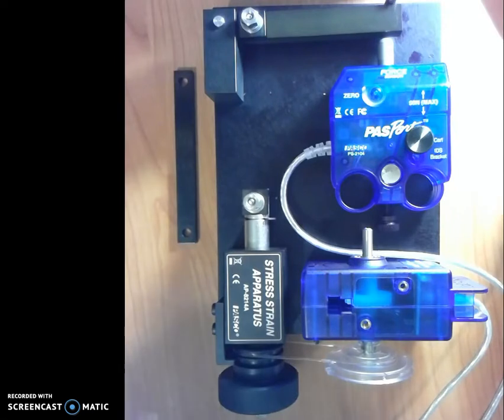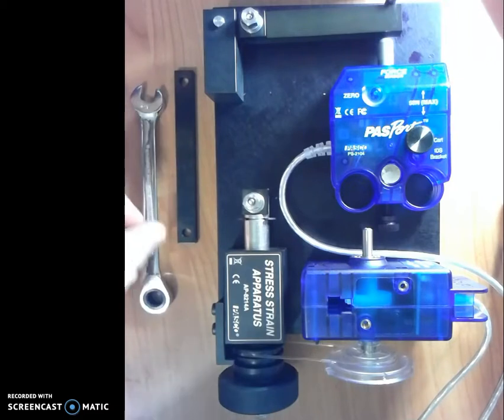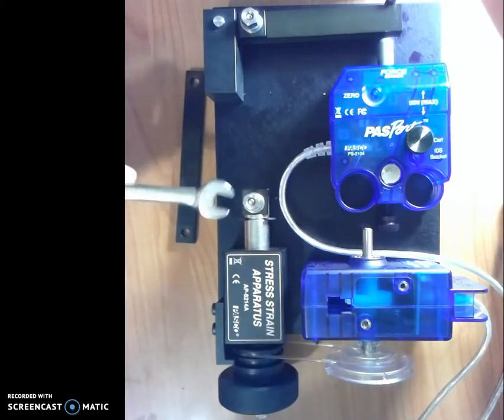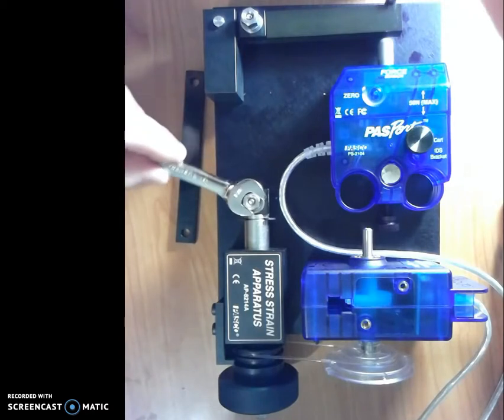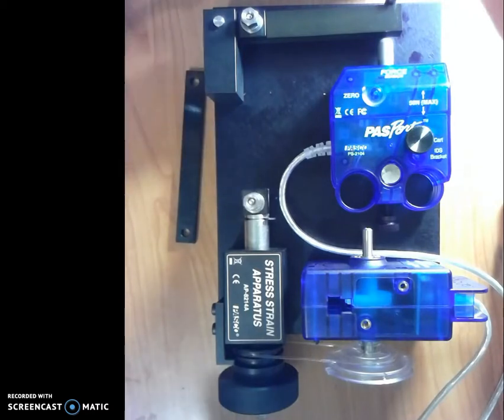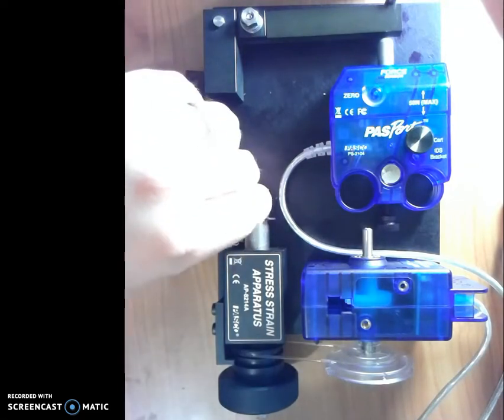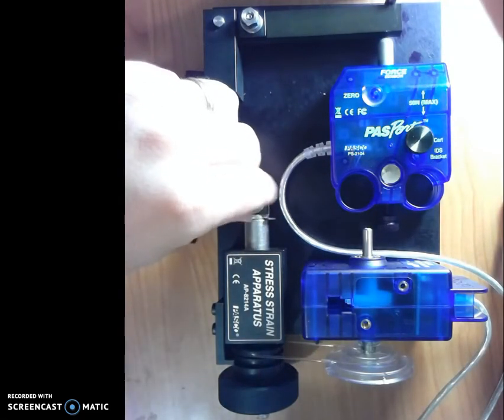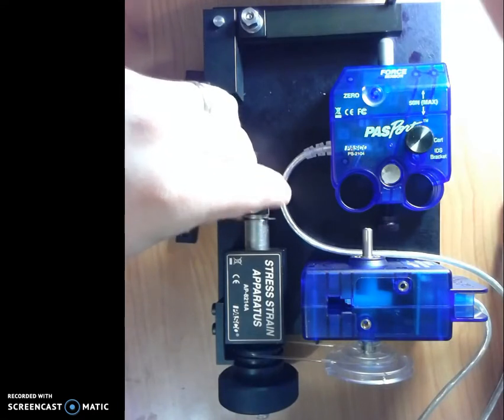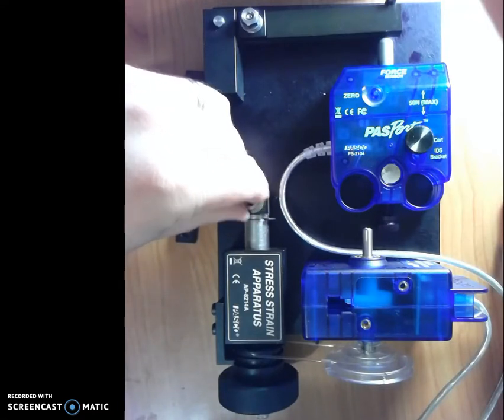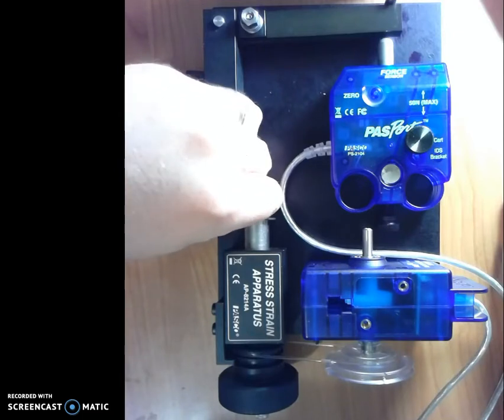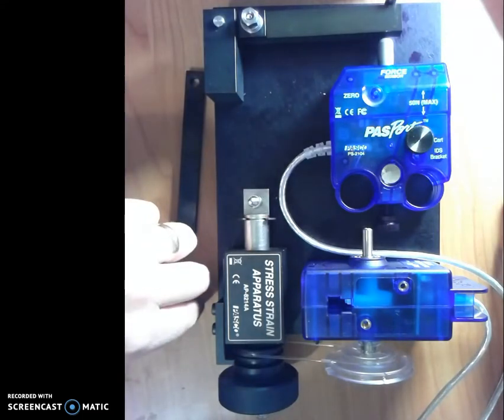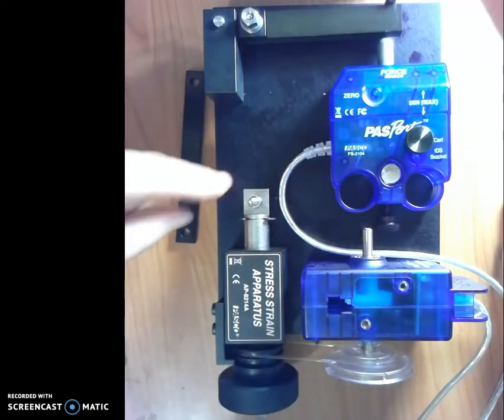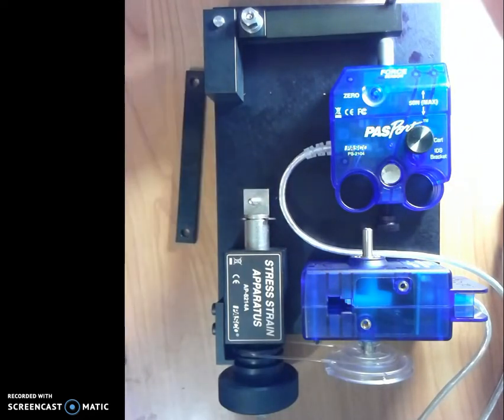Okay, so in order to do this, I've got a couple of nuts on here. I don't think I'm going to need it, but just in case, I've got a 3/8 wrench, which will fit over the nuts and tighten them and loosen them if I need that. I don't think I will, because I'm going to try to keep everything finger tight, but just in case, it's there. So what I'm going to do then is pull these guys off. So just unscrew the nut on the displacement arm, and I'm just going to pull this off, everything in the same order, and sit it aside here out of view. There's a little spring on here which I'm also going to pull off and keep with me.